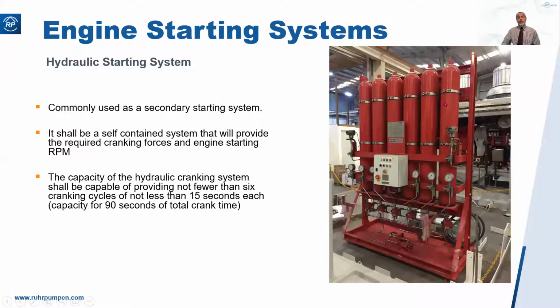As I said, they're very big, so more common and more popular are hydraulic systems, which are much more manageable from a size viewpoint. And also, in the event of a power failure, an example I would give you, a real example from when I was with Peerless Pump, there was a fire on an offshore platform. They abandoned the rig, and when they went back, the electrics were all down, but there was a hydraulic backup system on the fire pump. So they were able to manually pump it up.